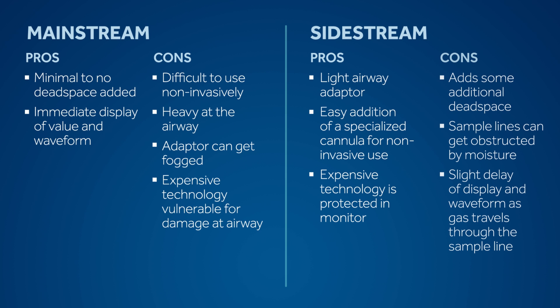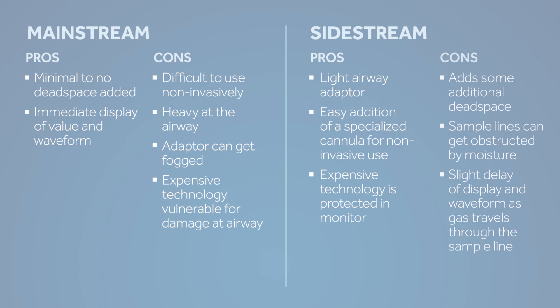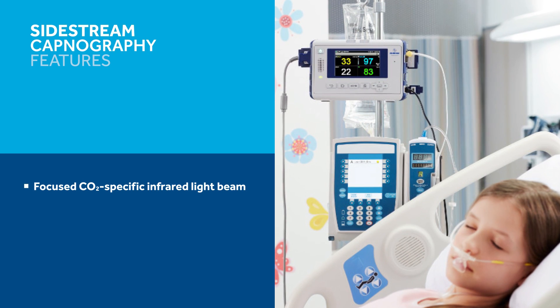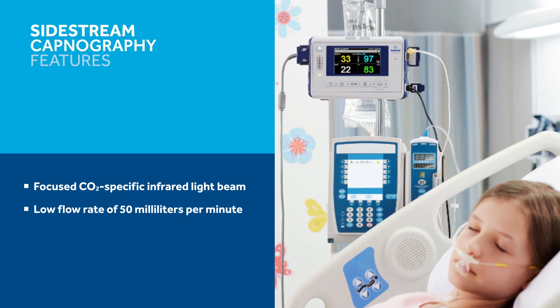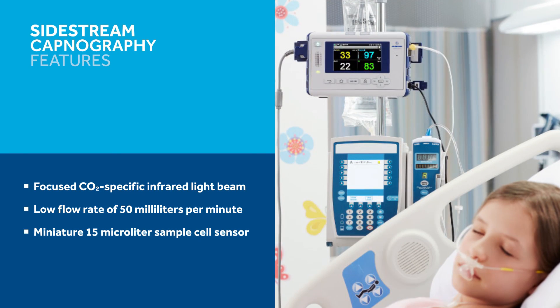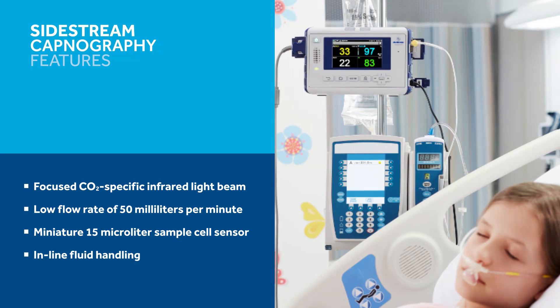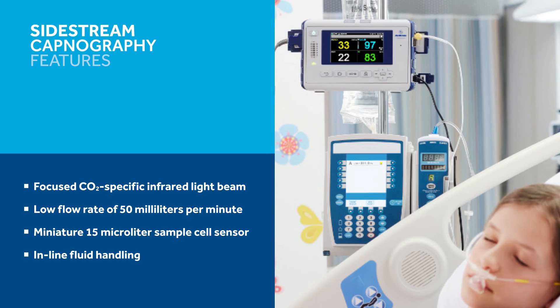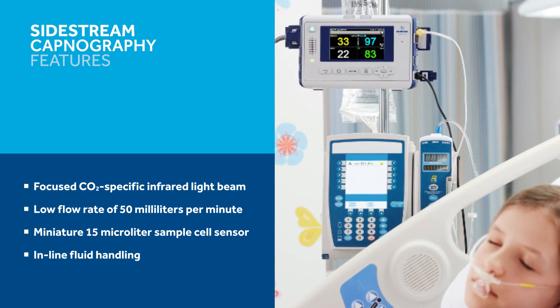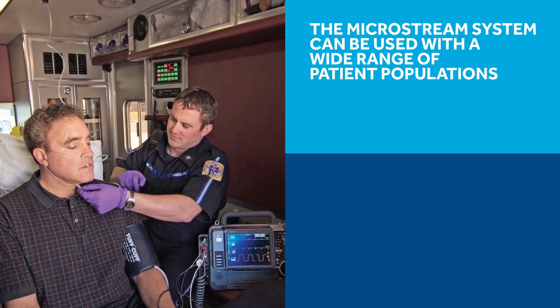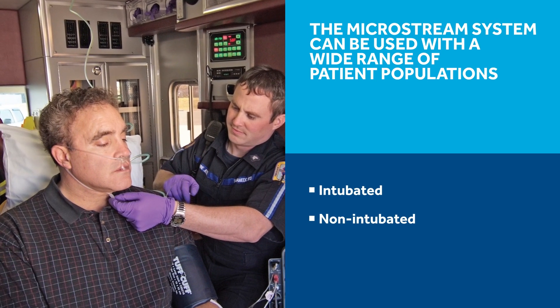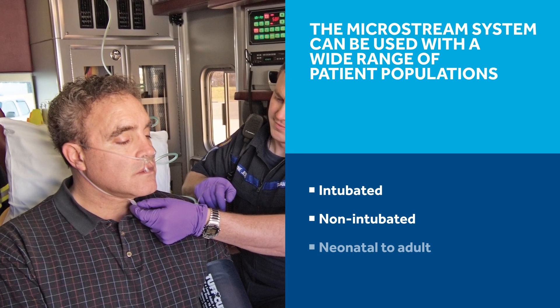Microstream CO2 sidestream sensors and breath sampling lines address some of the limitations of conventional systems. Microstream technology features a focused CO2-specific infrared light beam, a low flow sample rate of 50 milliliters per minute, a miniature 15 microliter sample cell sensor, and in-line fluid handling. Non-invasive measurement of ETCO2 can be achieved while oxygen is being delivered without diluting the sample. The microstream system can be used with a wide range of patient populations, including intubated and non-intubated patients, and all patient ages from neonates to adults.